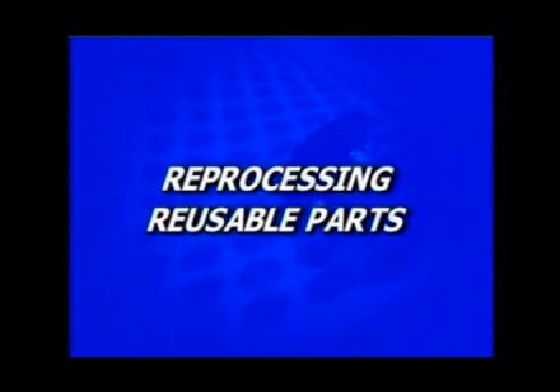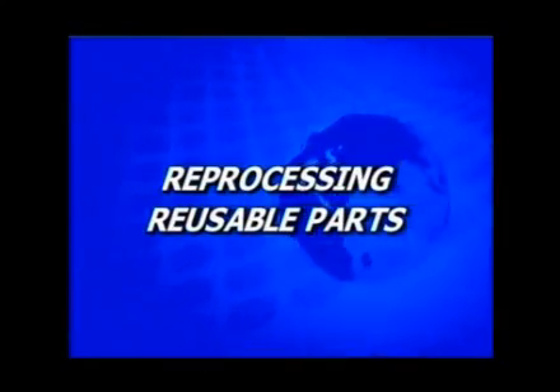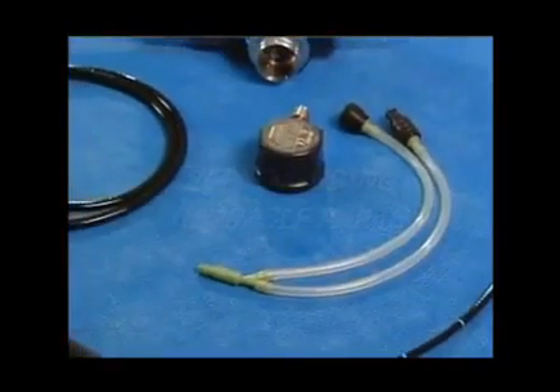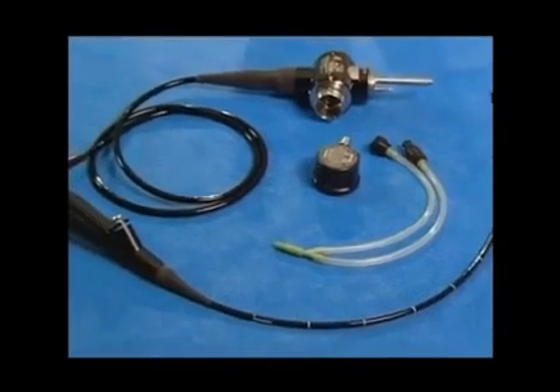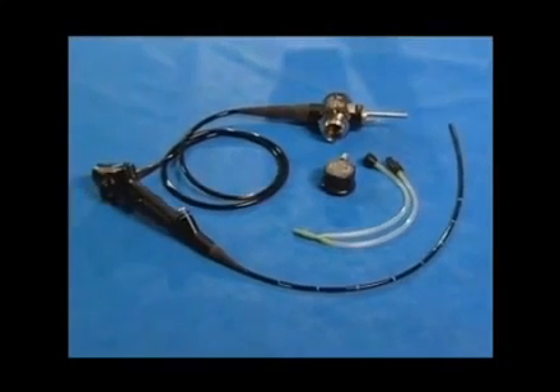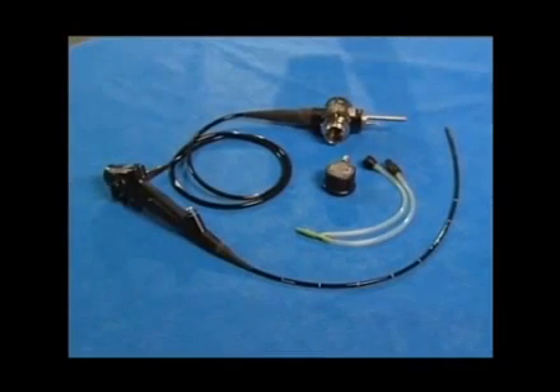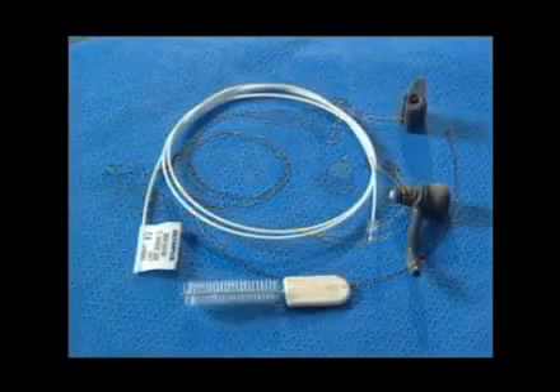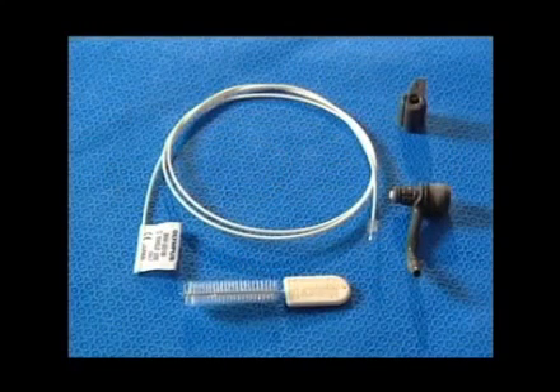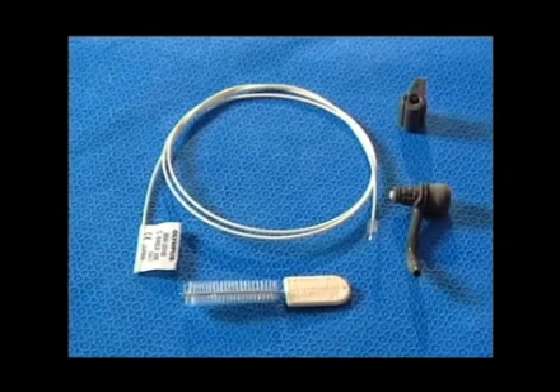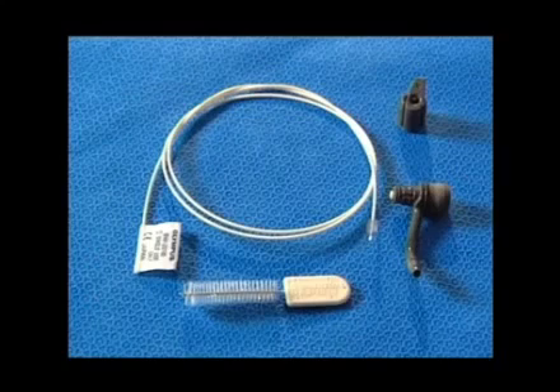Now that the bronchoscope has been reprocessed and stored, a few words regarding the reprocessing of ancillary equipment. Note that the water-resistant cap and the suction cleaning adapter have been reprocessed along with the bronchoscope. In addition, all single-use disposable items should have been discarded. This includes the suction valve, biopsy valve, and any single-use cleaning brushes.